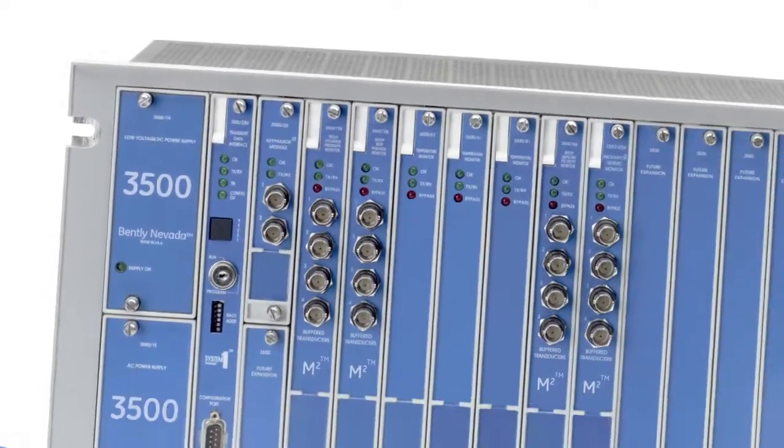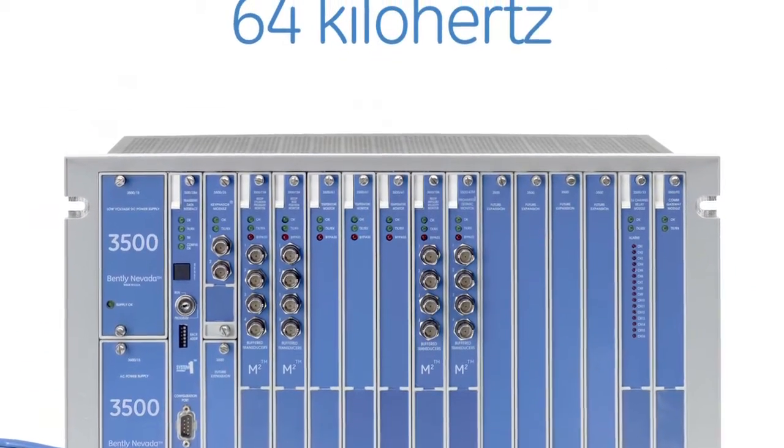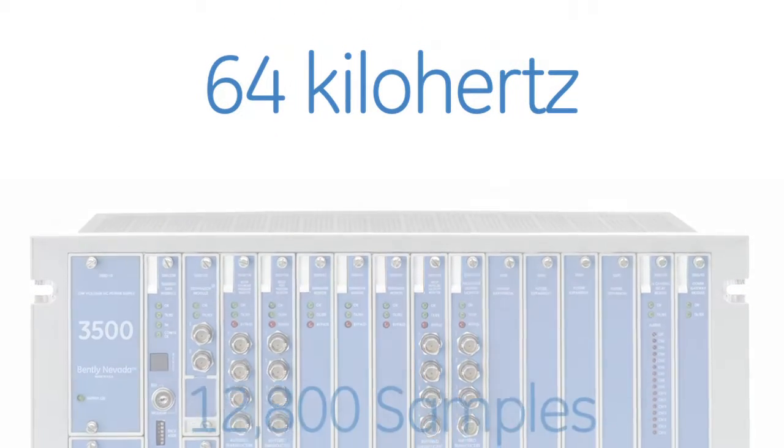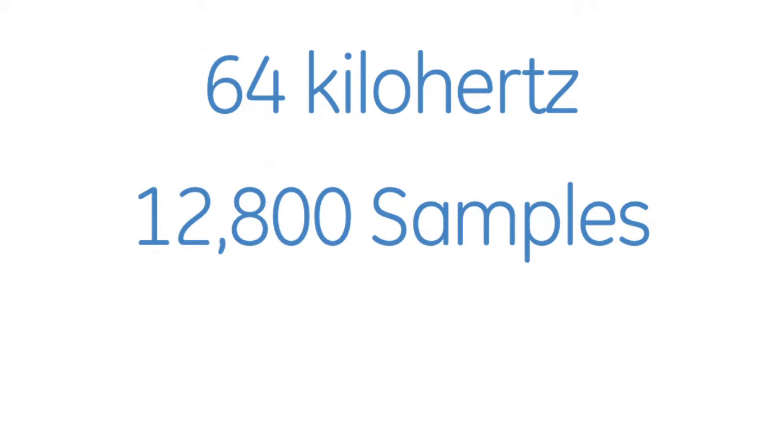To compare segmental bands, we start with 3500 monitors and our industry-leading sample rate of 64 kHz. For a typical 300 rpm, we sample 12,800 times per revolution.